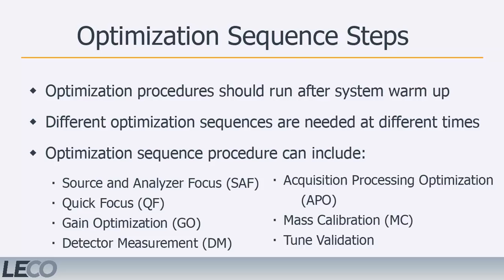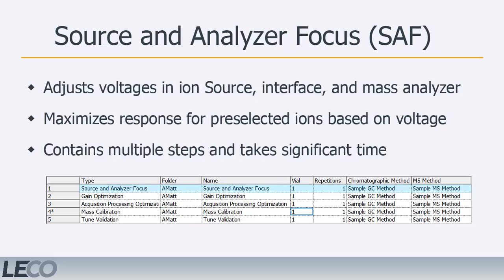and mass calibration. Source and analyzer focusing, or SAF, should be performed daily and will automatically adjust voltages in the ion source, ion interface, and mass analyzer to reach the maximum response for signal while still meeting the minimum resolution requirements.